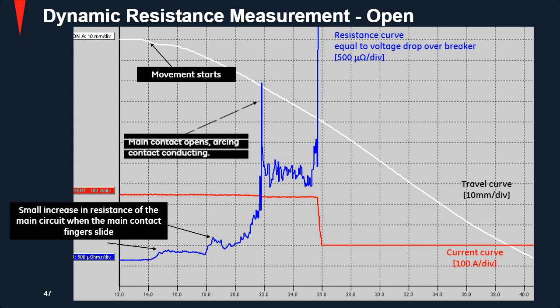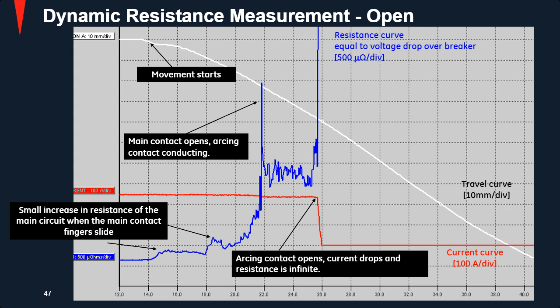And then your main contact opens and the arcing contact is conducting. Once the arcing contact opens and the current drops and the resistance is infinite, you can then, based off these two spikes right here, so spike 1 where your main contact was opening and the arcing contact took over, and then spike 2 is where your arcing contact, the arc was extinguished and you're in a safe state, the breaker was open and stationary.